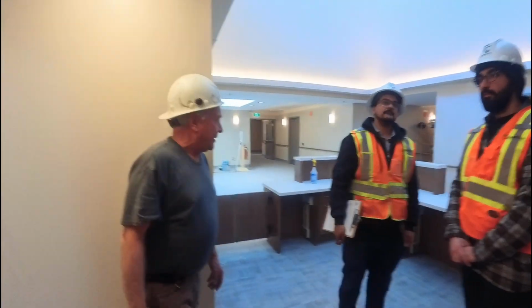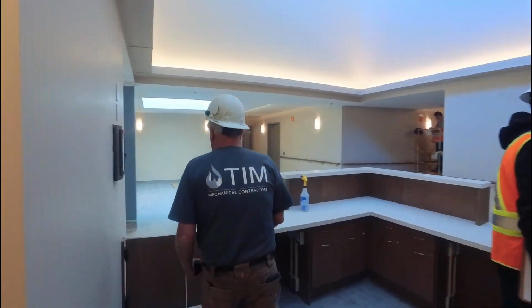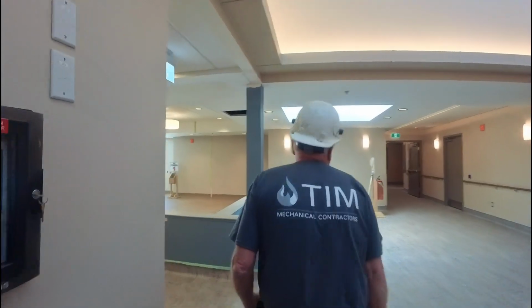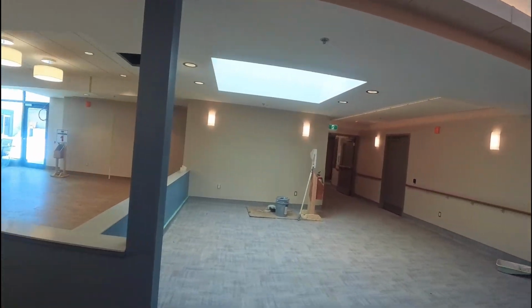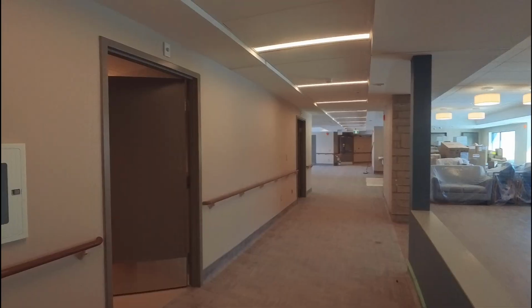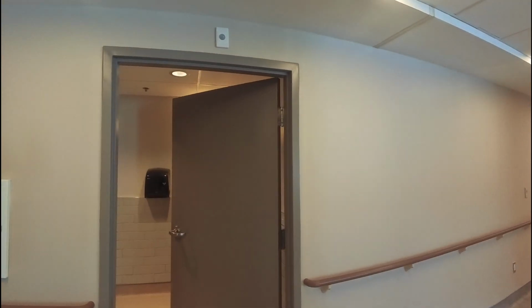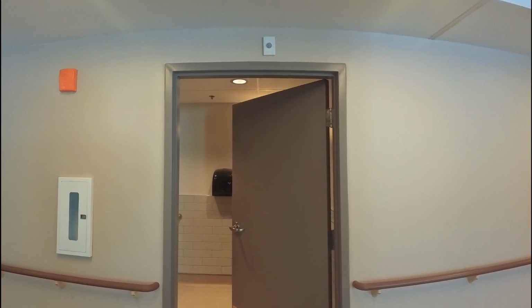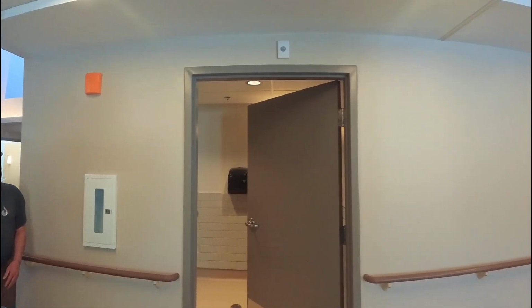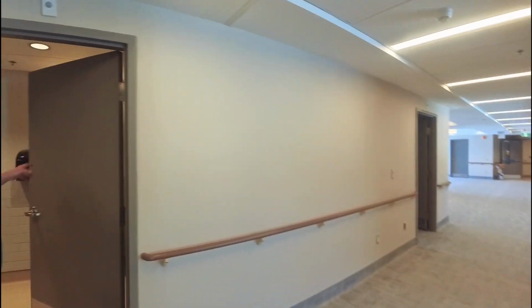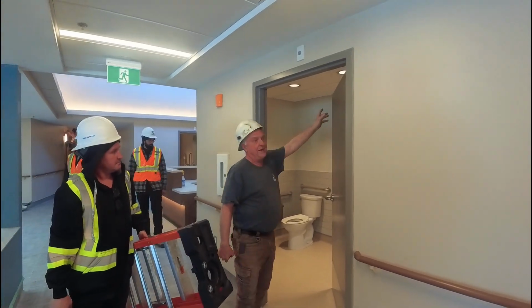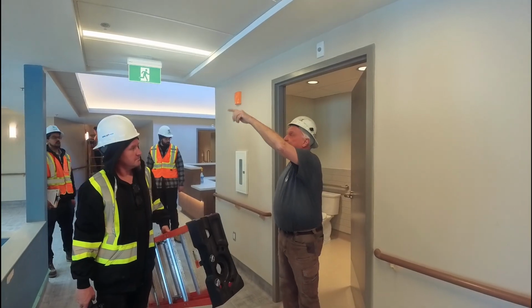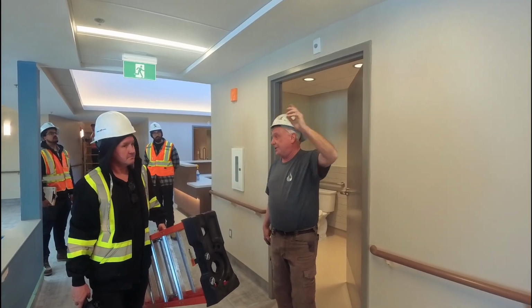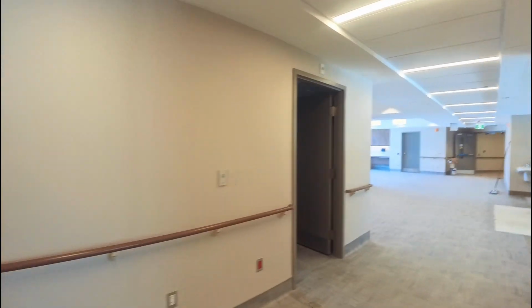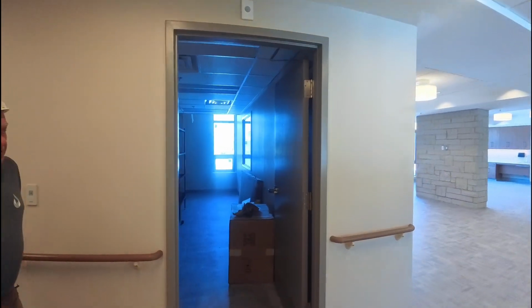And the third one is down around the corner here for the nurses. Yeah, why don't we actually take a tile out down on that guy and you can see. That bathroom and the bathroom coming out of the hallway we're just in, each one with an 8x8 exhaust. Again, that's just coming off of this makeup air unit right here, pulling 2 bathrooms back into the, similar to the exhaust that's in the suites.